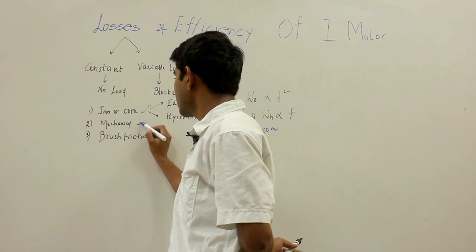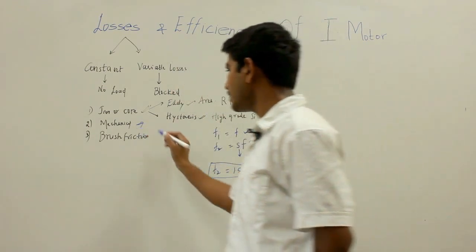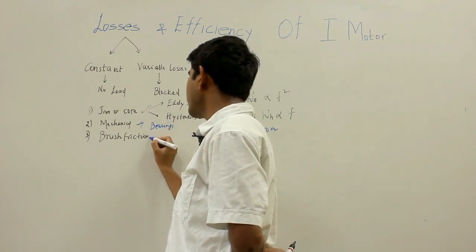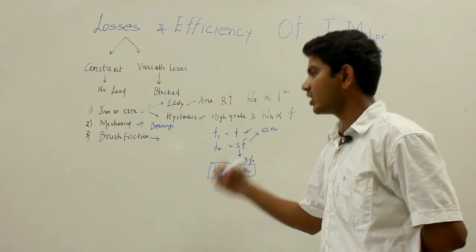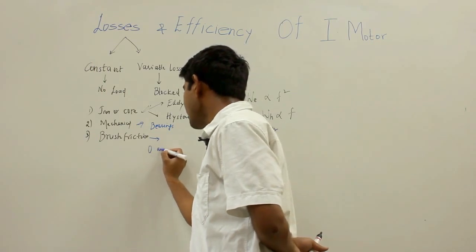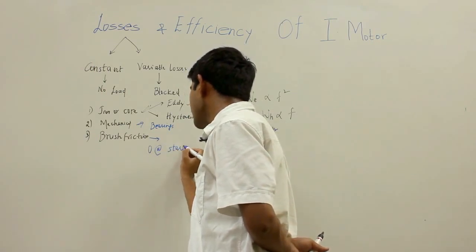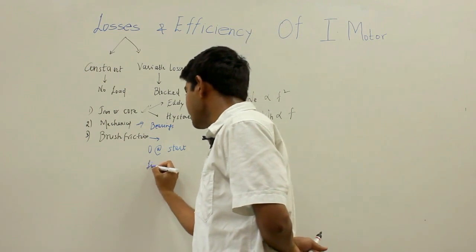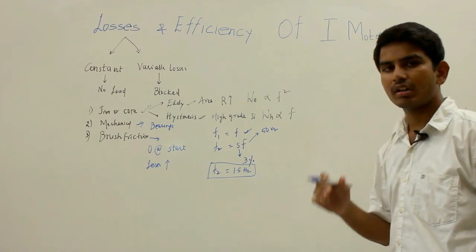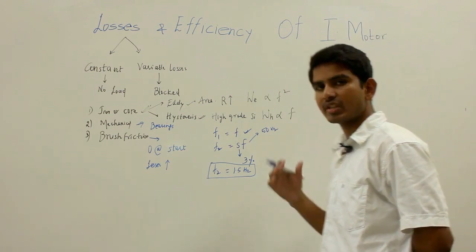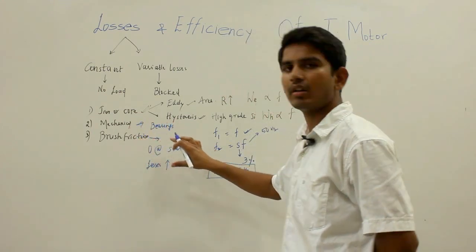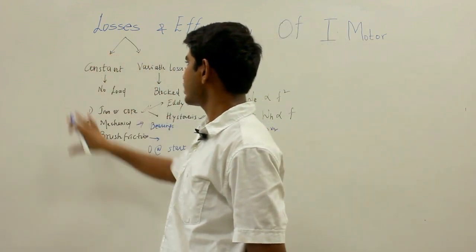Mechanical losses are those losses which occur at the bearings of the motor. Brush friction losses occur in the slip-ring type of induction motor; these losses are zero at start and increase as the motor gains speed. However, in the three-phase induction motor, speed remains almost constant, so mechanical losses and brush friction losses also remain almost constant.